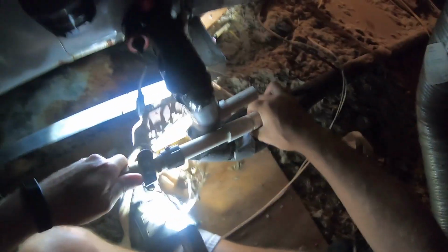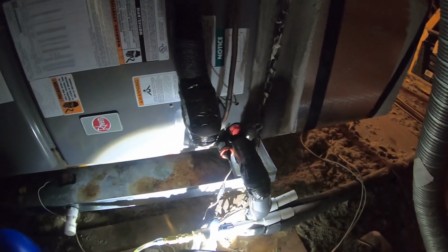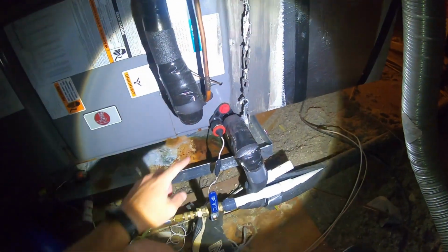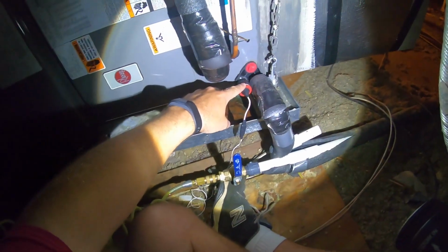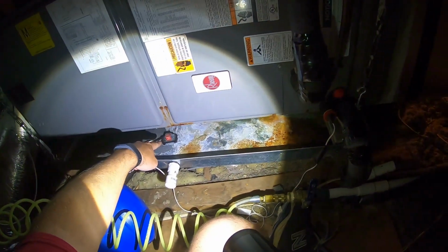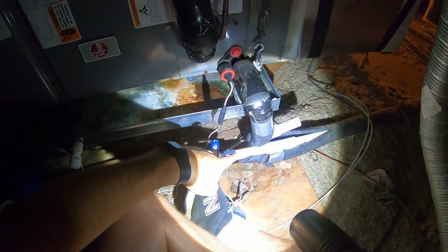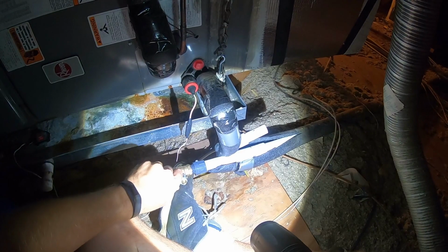So now we do. Notice that this is apart now. You can see there is some snot in there, not too bad. Slide that in there. Hopefully you guys can see all this. Let's check and make sure. So here is that sensor I showed you before, the primary sensor. There's the backup sensor, the pan, and we have our apparatus hooked up here. Now we're just going to send some air through it. And bursts. This is the kind of stuff that builds up.